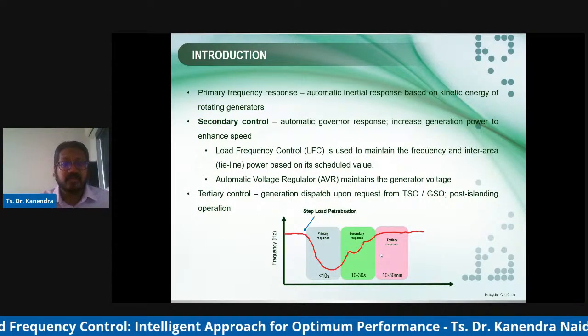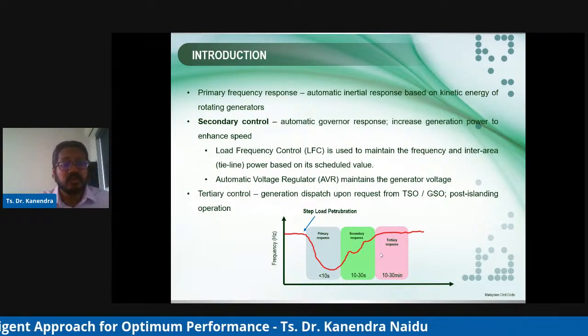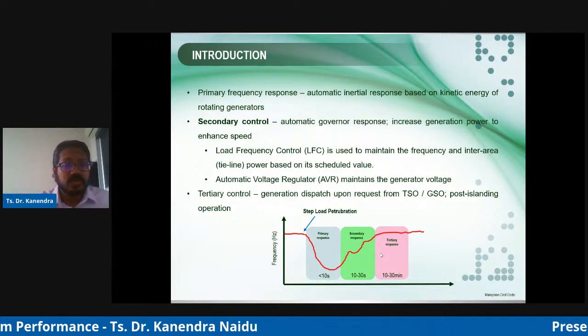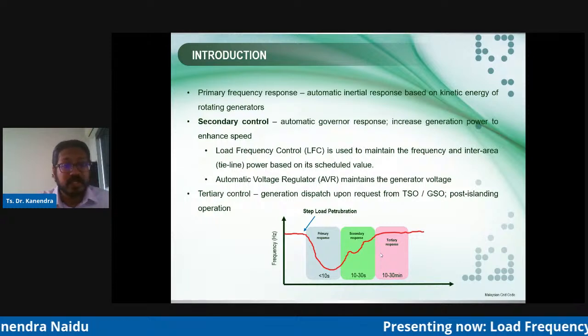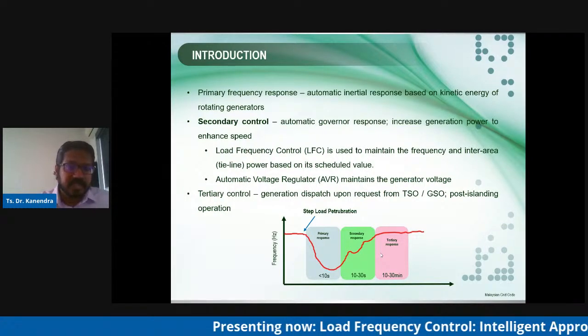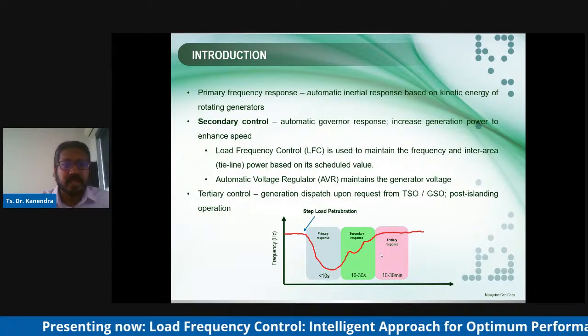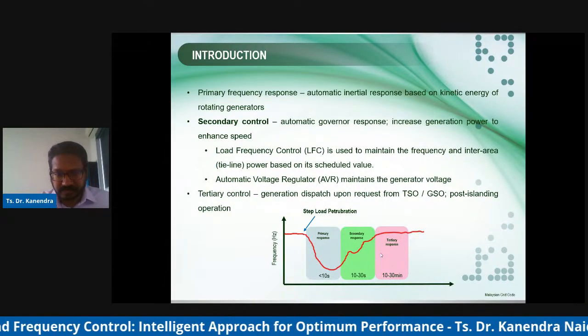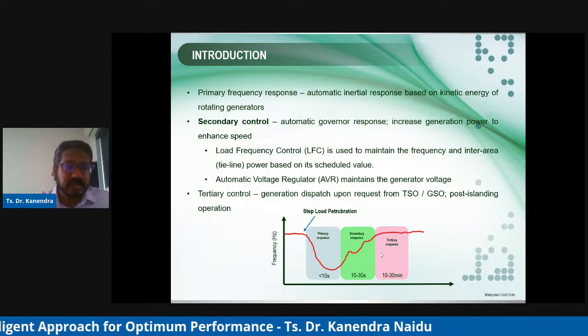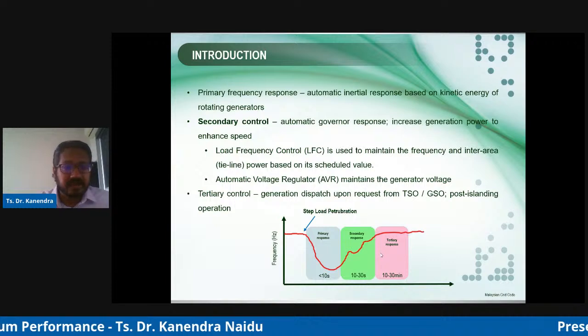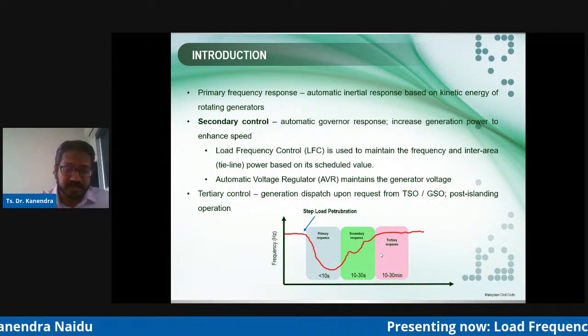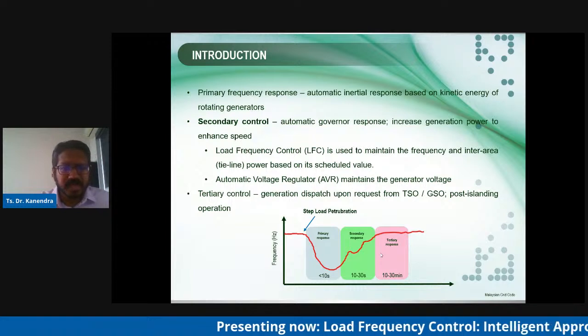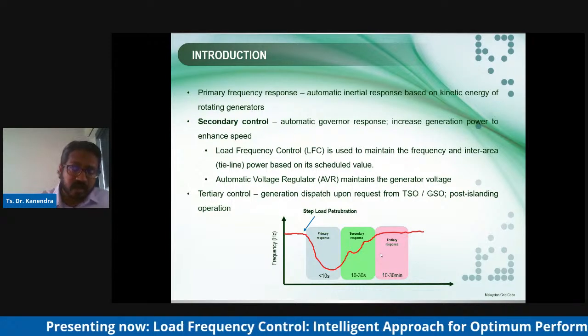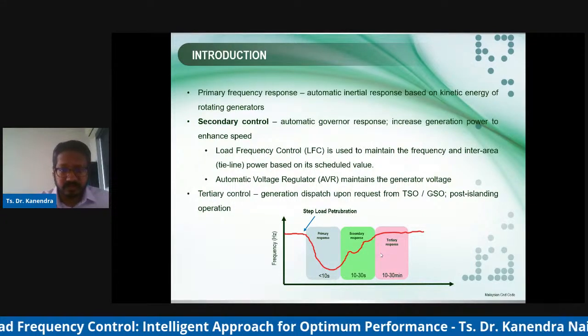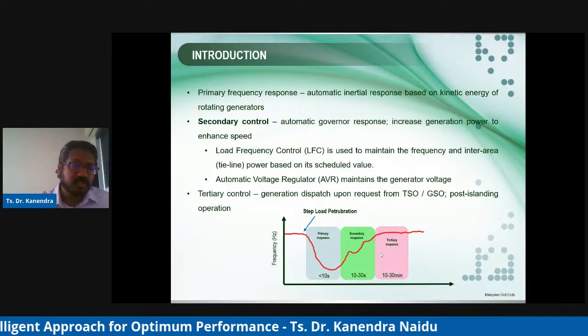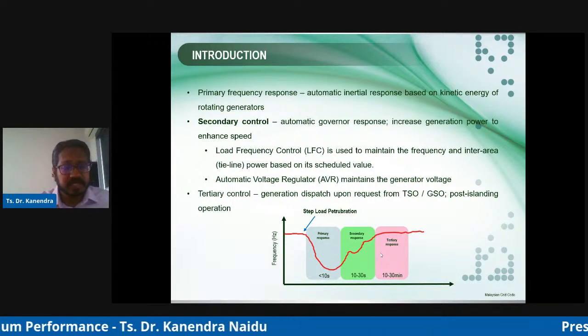Further than that, the secondary controller kicks in, which is the governor response, and then the load frequency control, or LFC, will play its role to try to bring the system back to nominal condition, or the reference frequency. That is being done by the LFC, and the AVR will do it for the voltage. And when we go to tertiary control, it is more than the 30 seconds limit. We are talking about generation dispatch, redispatching generation. This can be seen in post-islanding operation. So when you island the system, when you carry out ICI, you are able to see that certain islands will have load rich or generation rich. So they have to redispatch the generation.